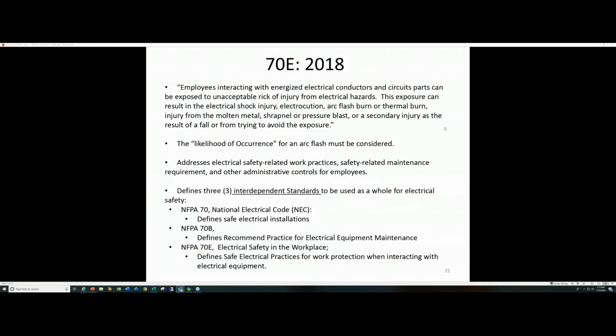Let's talk about 70E. In 70E 2018, there's a couple of things. They say employees interacting with energized electrical conductors and circuits can be exposed to unacceptable risk of injury from electrical hazards. This exposure can result in, like I was saying earlier, shock, electrocution, arc flash, thermal burn, molten metal, like I explained with the copper plasma, shrapnel, and pressure blast. And you can also have secondary injuries, like knocking them off a ladder, or their physical reaction to avoiding the hazard could put them at risk by jumping off a platform or running into something, those kinds of things. 70E addresses electrical safety work practices, safety-related requirements, and other admin controls, like I said earlier.